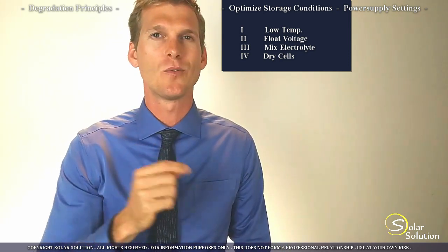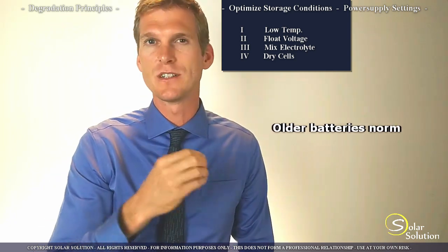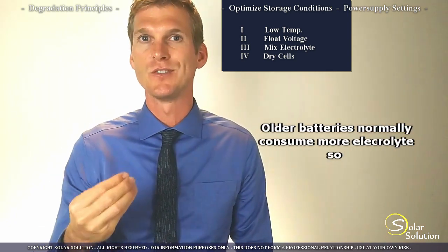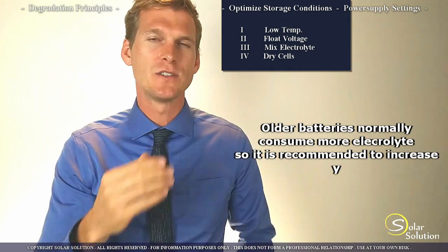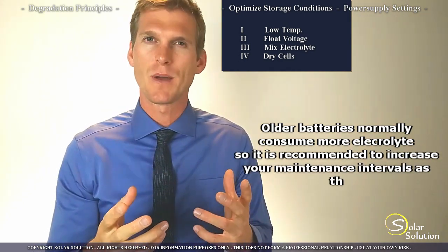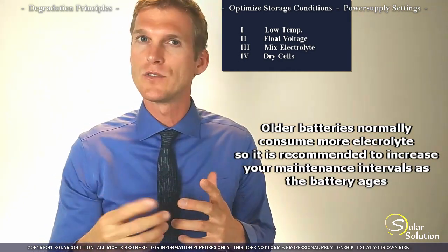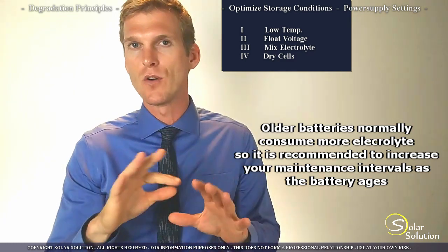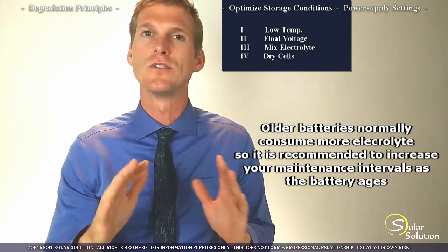So please remember that old batteries they use more water over time. A new battery doesn't require that much top up but old batteries do. A new battery to give an example, a 200 amp hour flooded lead acid battery uses in float stage about a liter of water per year so you should at least check that battery every four to six months.